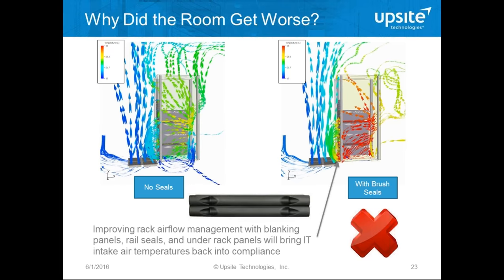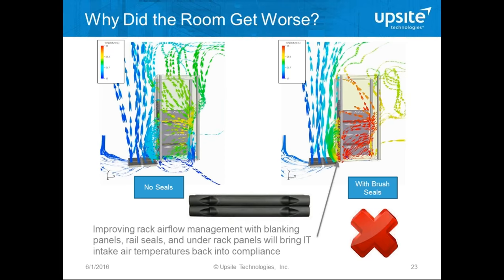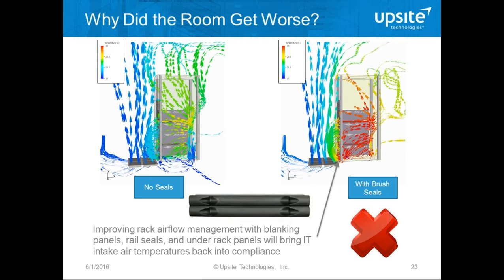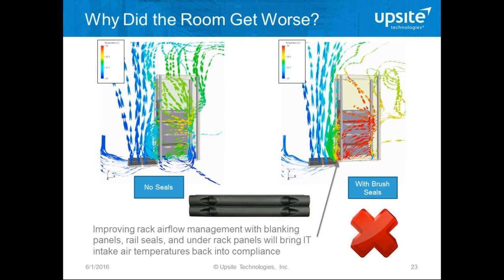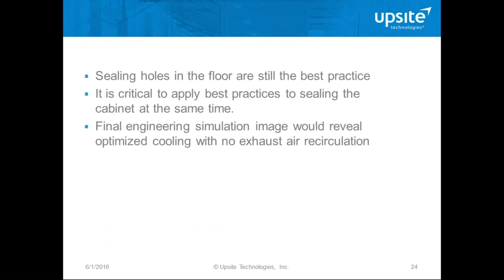What we need to do is blank the gaps. Everyone is aware of putting in blanking plates between the IT equipment between the mounting rails, but we must also consider the areas around the mounting rails at the sides, and under and over the IT equipment. Sealing holes in the floor is good practice, but it's critical to apply the same best practice to the cabinet. A final engineering simulation would reveal optimized cooling with no exhaust air recirculation.